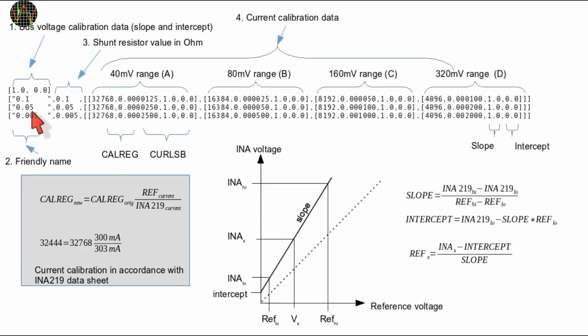Each line is made of 3 parts. A friendly name that could be anything meaningful to help you identify and select that dataset, because that is the text shown in the setup menu. But it can't be longer than 8 characters. The next part is the nominal value of the shunt resistor in ohms. This is followed by 4 sets of 4 numbers each that make up the current calibration data for each of the shunt voltage ranges. I named them A to D because that's the range designation I use on the LCD display.